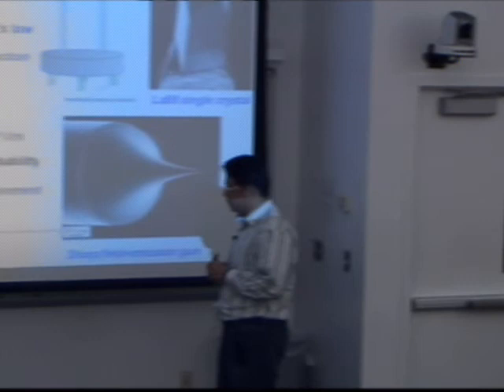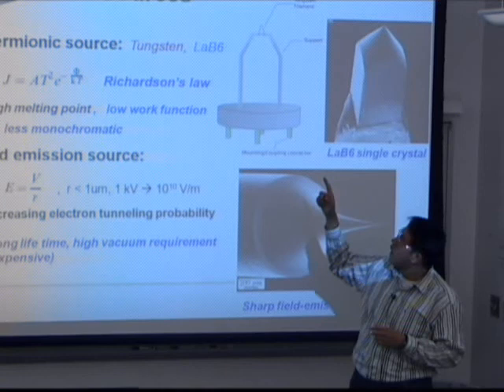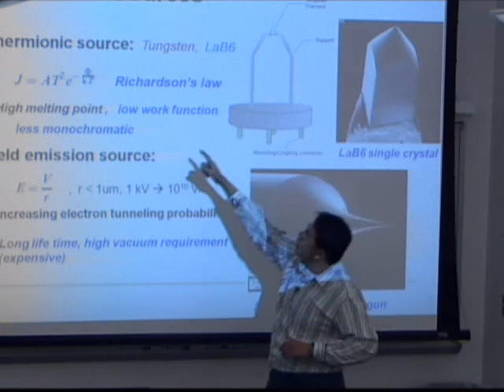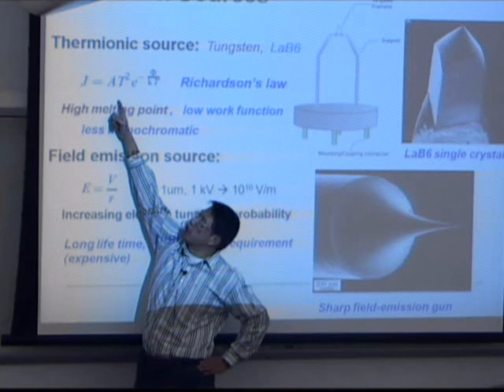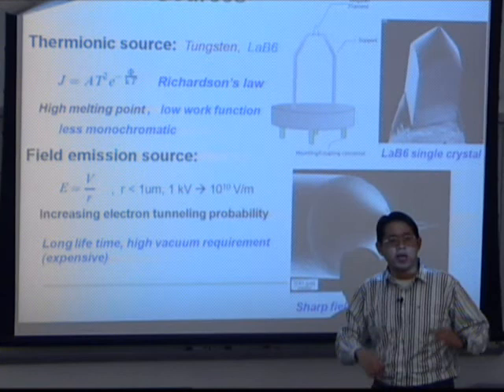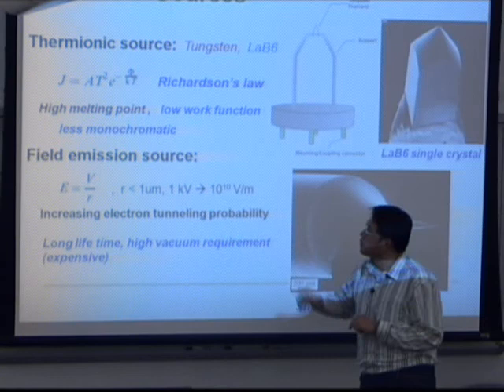Now let's talk about the electron source, which is very important — it's the beginning of getting the image. There are two types of thermionic sources: tungsten and lanthanum hexaboride (LaB₆). There are also field emission sources. The thermionic sources are governed by the Richardson law, where the current density is proportional to the square of the temperature and an exponential depending on the work function φ. A higher melting point material like tungsten allows higher temperatures and more current density. LaB₆ is used because it has a smaller work function.